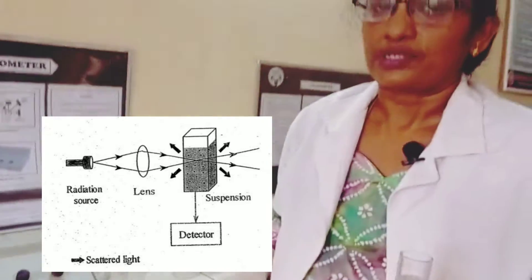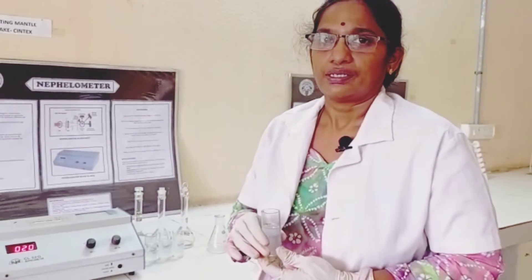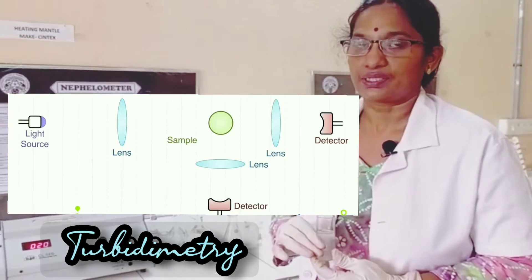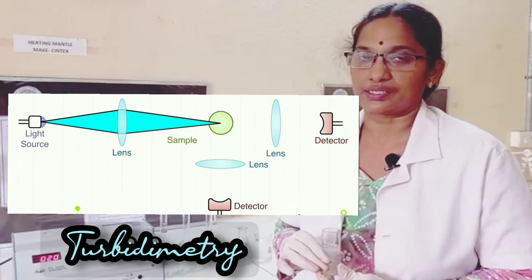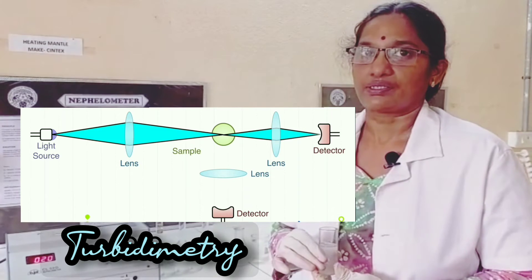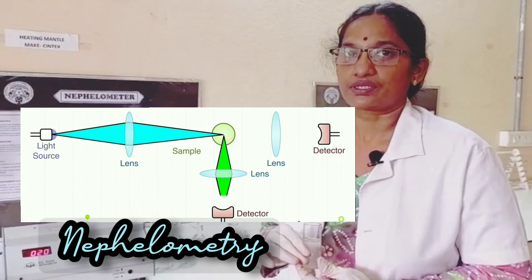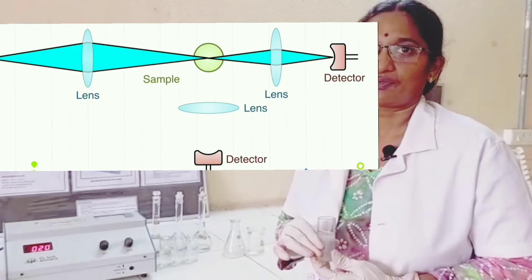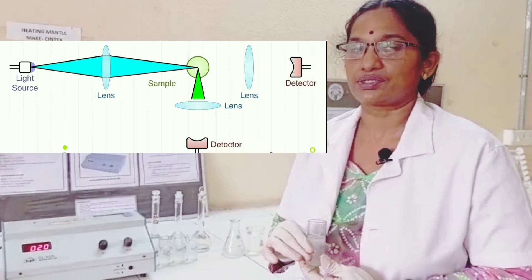Nephelometry is almost similar to turbidimetry, which is also a method where we can estimate turbid solutions. Turbidimetry measures the amount of transmitted light after passing electromagnetic radiation through the suspension. In nephelometry, we measure the scattered light — specifically, the intensity of the scattered light which is scattered by the suspended particles. Whereas in turbidimetry we measure the amount of light transmitted. This is the key difference between both methods, which are both used to measure suspensions and turbid solutions.